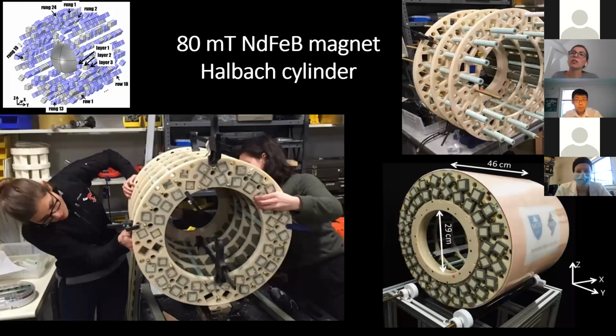Here are some photos of us actually building the magnet. We first created the magnet former, using ABS rings that we water jet cut squares into for the rectangular rungs, as well as some other places for support material and shimming magnets, which I'll mention in a second. We put the former together with some brass rods and fiberglass tubes, and then we used these green fiberglass square tubes to hold the actual permanent magnets. First we built the former, and then we pushed each of these 1-inch permanent magnets into the tubes in the configuration determined by the optimization, and bolted them into place. Here's the resulting magnet shown on the bottom right.